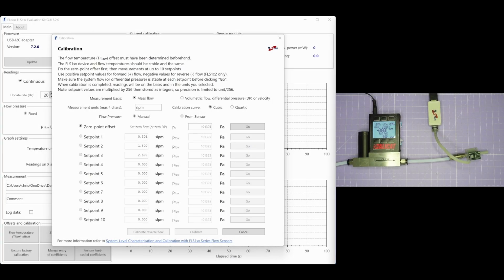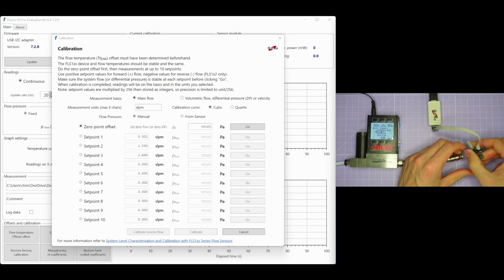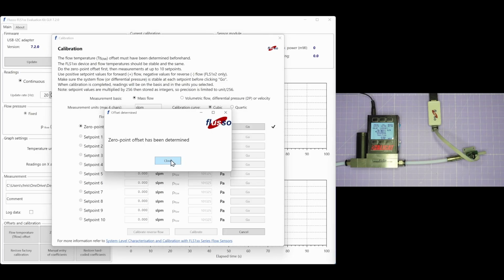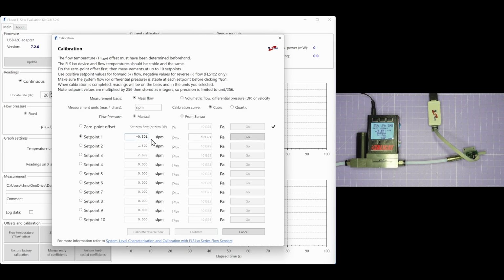If you want to perform a reverse flow calibration, just set the fixture up so that flow is passing in the opposite direction. And then enter negative set points in the calibration procedure. So again, we're going to perform a 0-point offset. And this time we're going to enter minus 0.3 litres per minute. Minus 1.5 litres per minute. And minus 2.7 litres per minute. And then we click Calibrate for reverse flow.